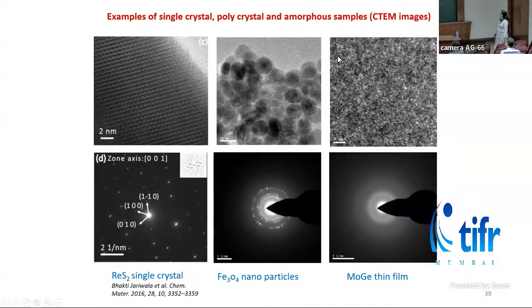Here are some examples of samples imaged using this TEM. So this is the diffraction pattern of a rhenium sulfide single crystal. By indexing and analyzing this diffraction pattern, we can identify the crystal structure of the sample.